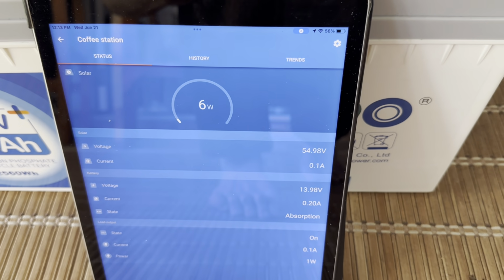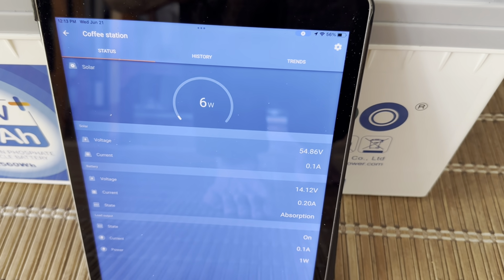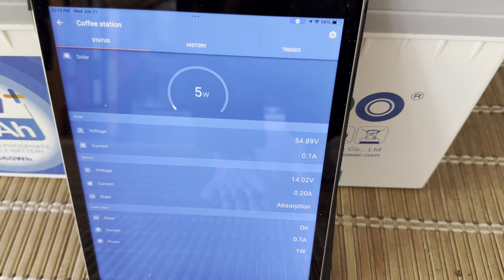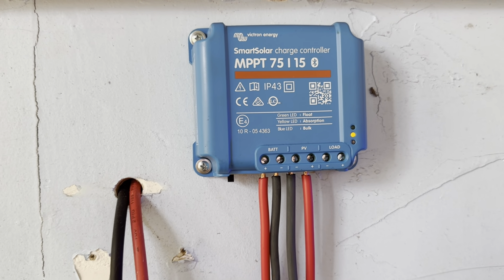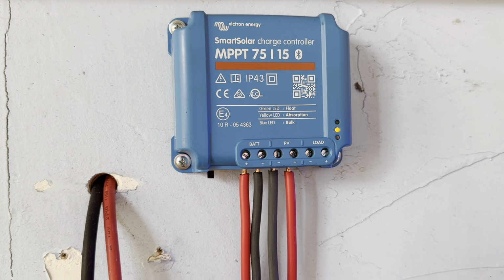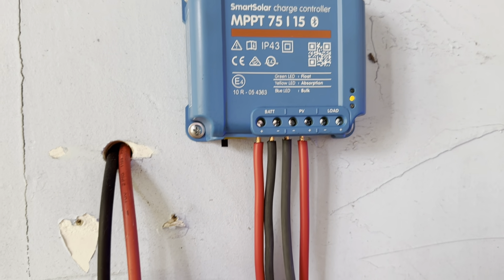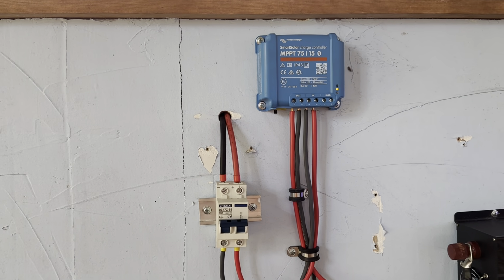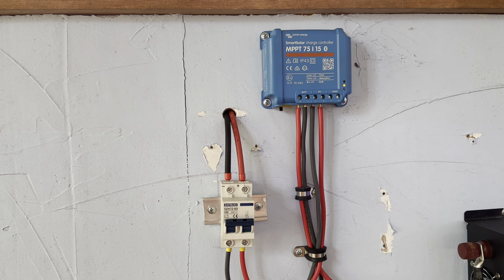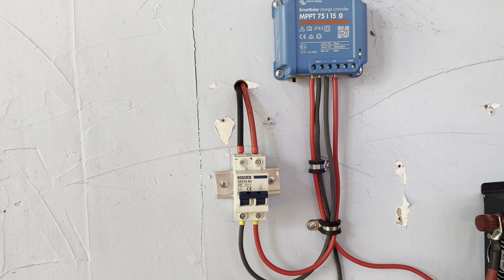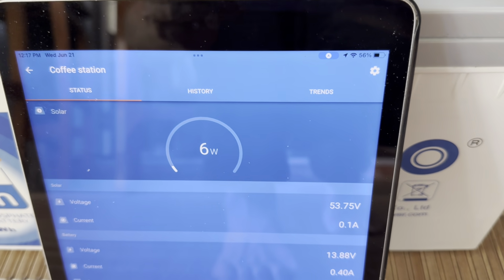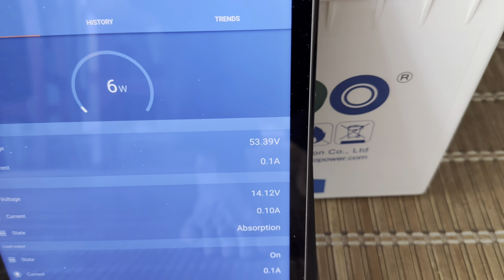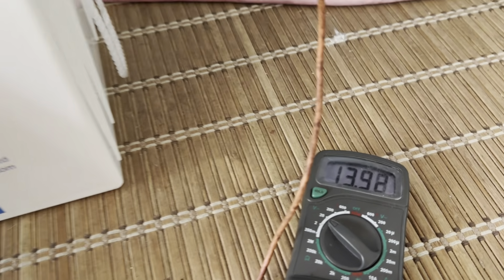So let's see if we can actually put a discharge on that inverter. We can see the charge controller with the yellow light on, indicating it's in absorption mode. This is the exact same size charge controller that was on that other system, and it did the same thing — it reads the battery as completely full in its absorption phase, allowing 6 watts to hold it right at 14 volts, which is what we have this charge controller set for.